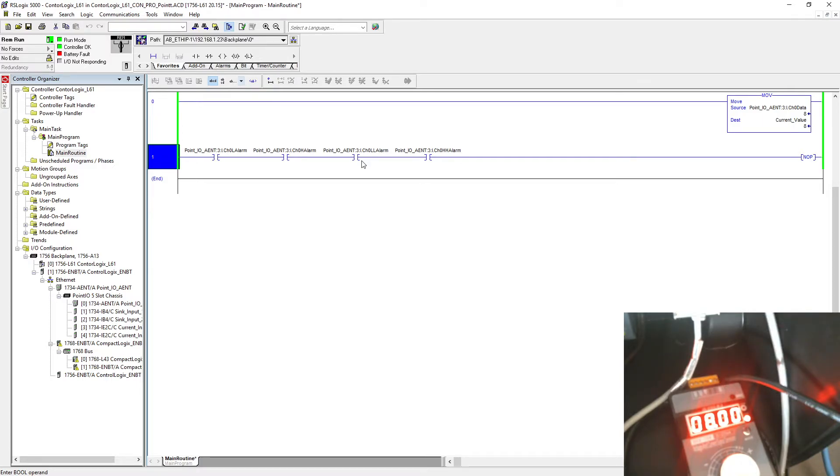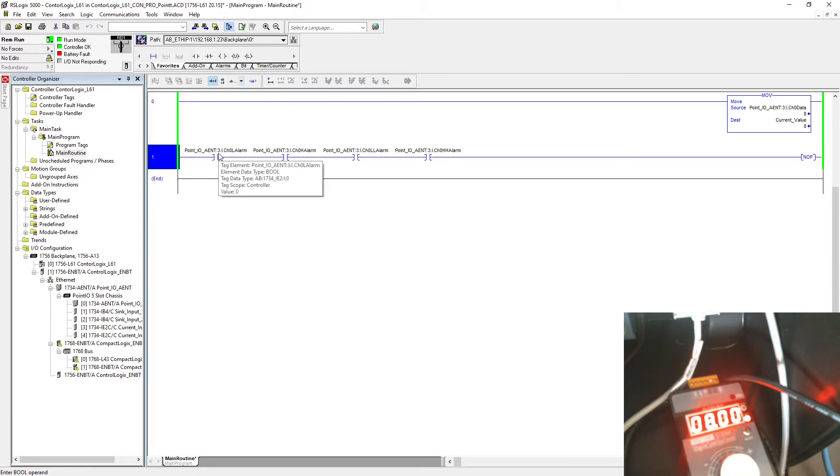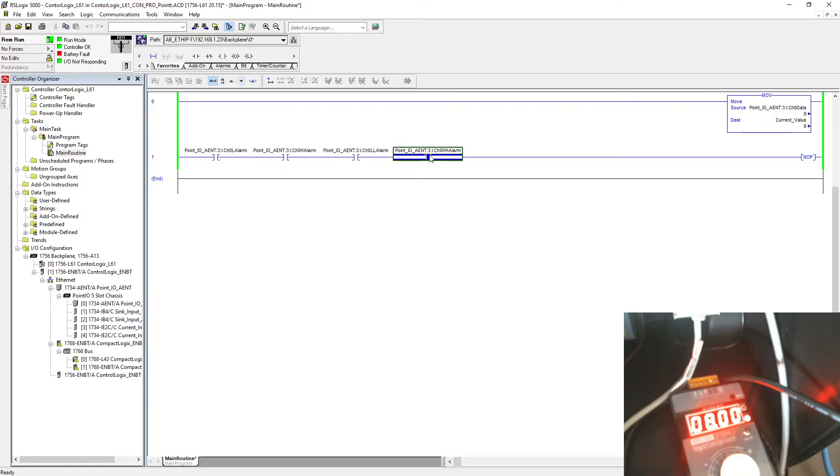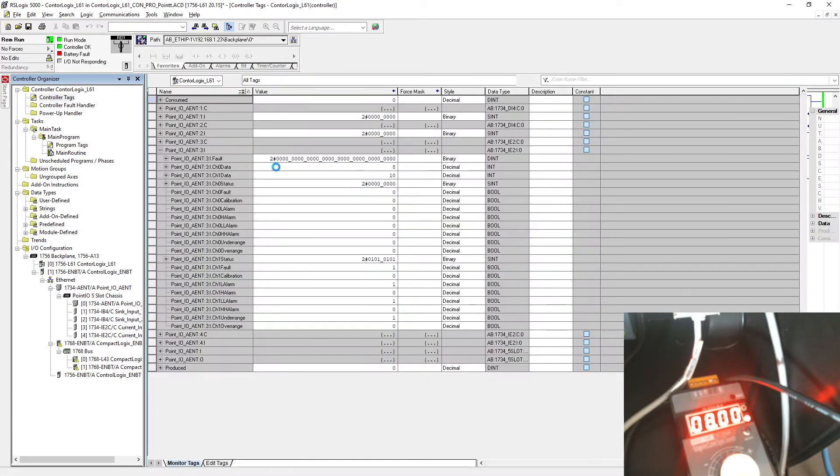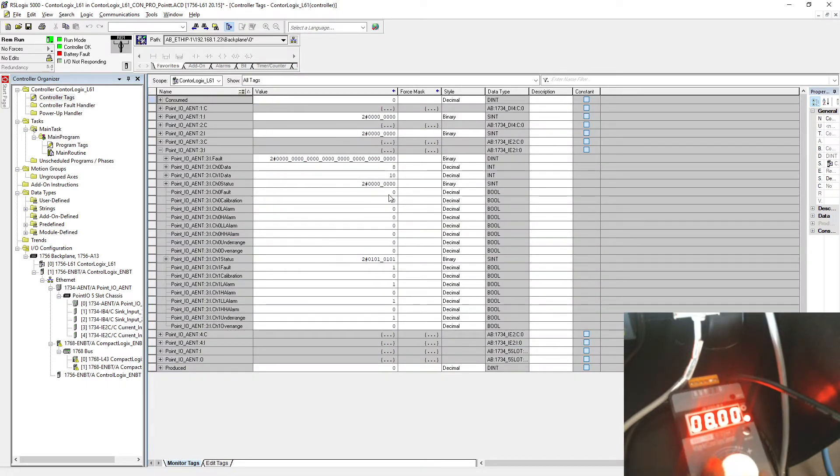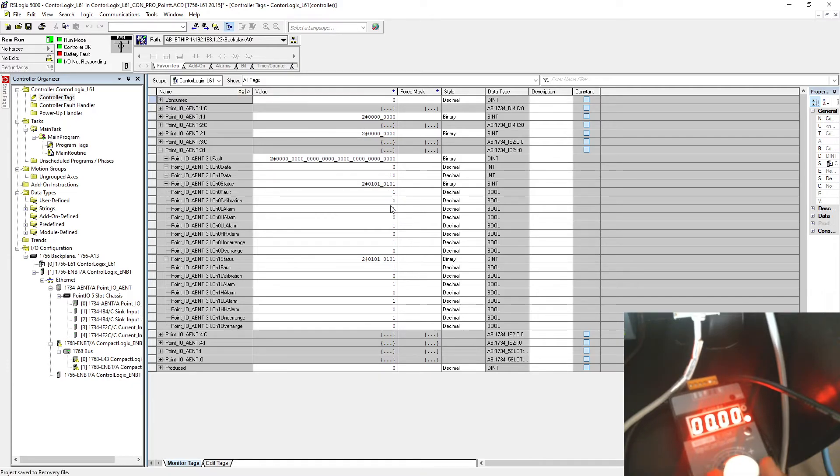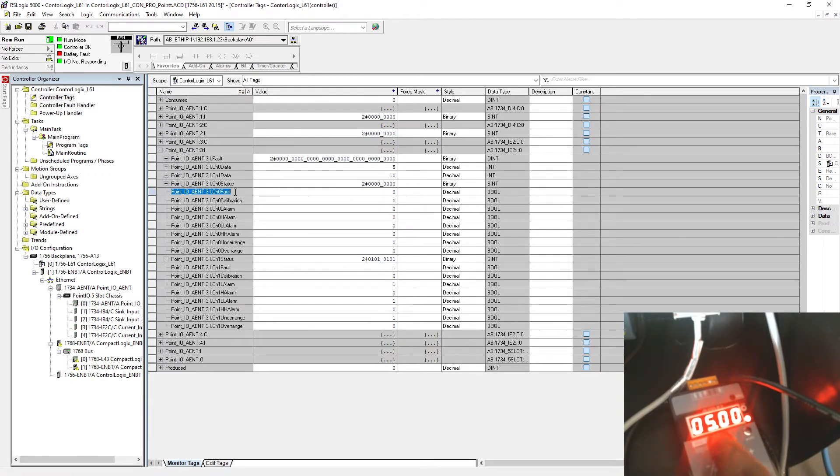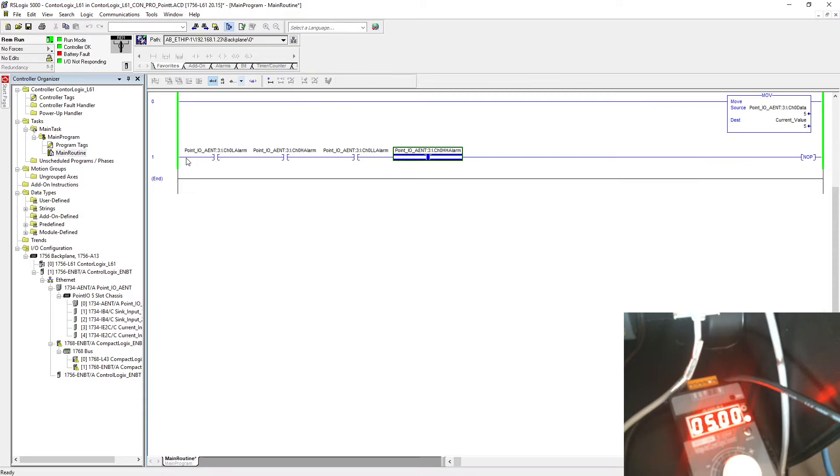These things you can use in your programming. So let's say you're pulling current data over here and you want to make some programming, you can do that because now you have all alarms given by your input card. Also, you can pull the fault as well. Whenever the fault turns on, you can see this fault bit also turns on, so we can pull this fault bit as well.